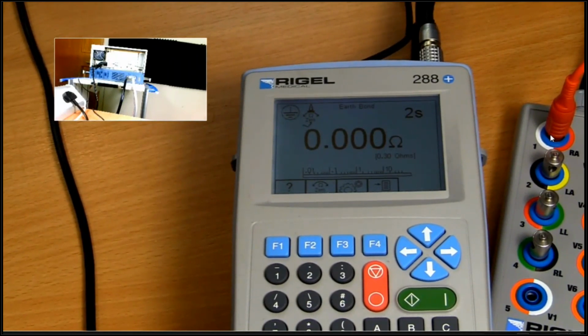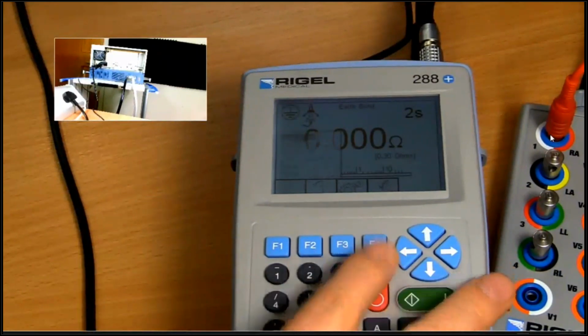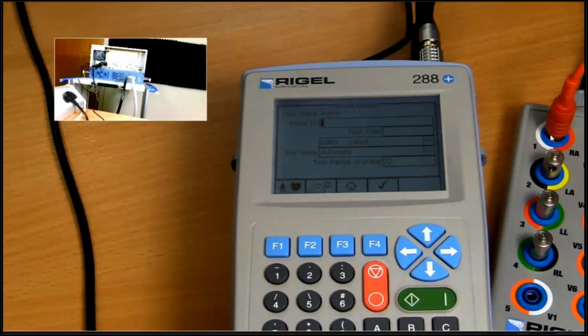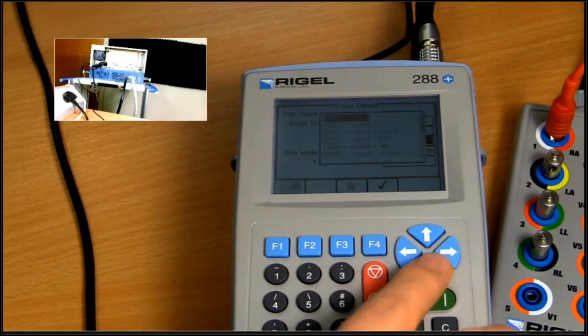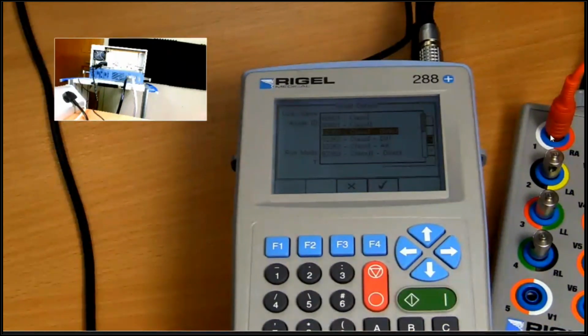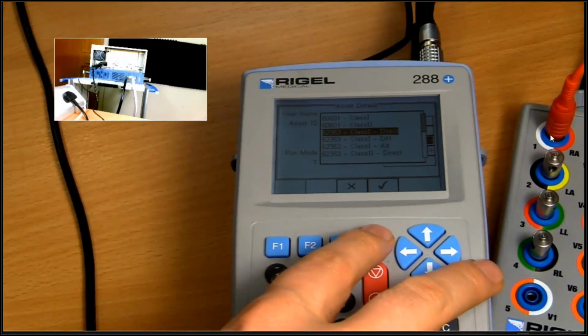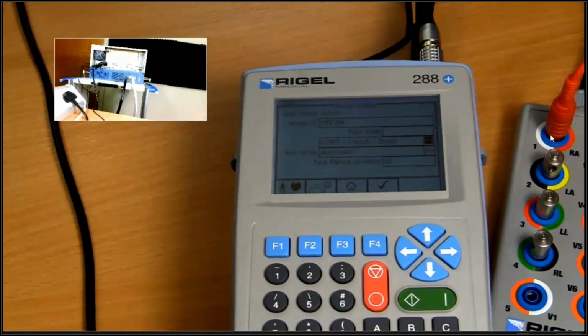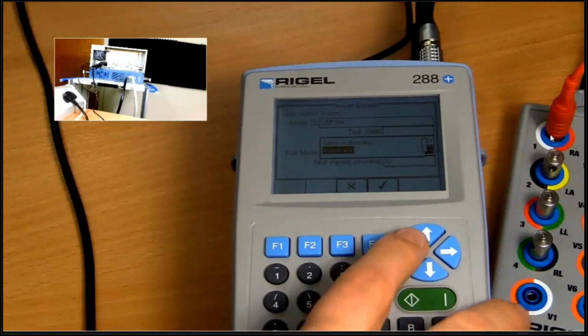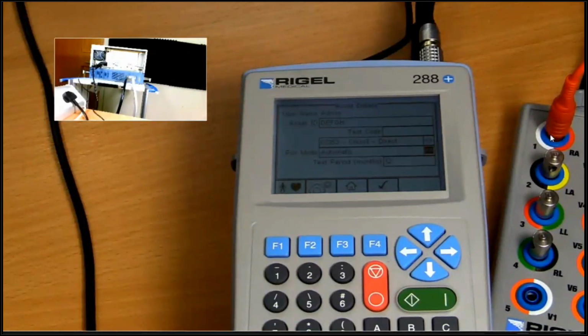It's very, very easy. So what I'll do is I'll press F4, press auto mode. If it has an asset ID, I'll put that in. For the purpose of this exercise, I'll just put anything in. This is not important. I'm going to select the class. I'm going to use 62353. It's a class 1 device, and I'm going to use direct because that's pretty much the commonly used test for class 1 62353 testing, very similar to 60601. I want to put this down as automatic. The run modes, automatic and semi-automatic, which you can see there, are used because you have to test leakages in normal use, in inverted commas.